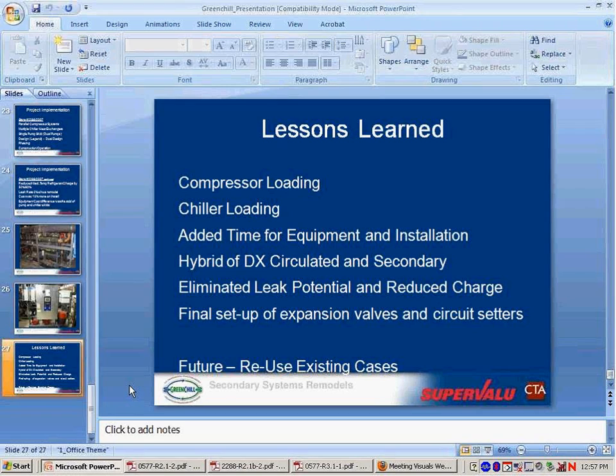By flow. What they did was identify a preset number by looking at the charts, and went with that. After the store was up and running, they looked at how often those valves would cycle, and from there would start closing it down to where you still maintained temperature. Temperature was a factor, but keeping that solenoid's cycling to a reasonable amount was the goal. Ideally, if you could maintain flow all the time other than during defrost, and set it perfectly, that would be the best scenario, because then you've got the least amount of flow needed to maintain temperature. But to answer your question, they closed it down and reduced the flow until those cycle counts were minimal.